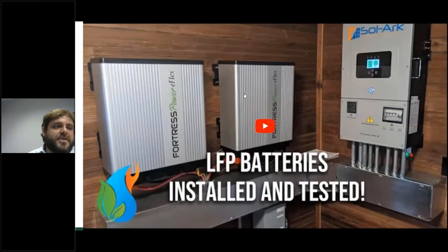And so, yeah, Drew, it's true. Every connection is a failure point, and in general, you want to reduce those failure points. But when we're talking about connections being put in a box, many installers will say it's worth adding an extra connection to put a fuse in line. We're not going to say you have to mandate it. If you don't, it's very rare to have a fuse blow in this type of instance.